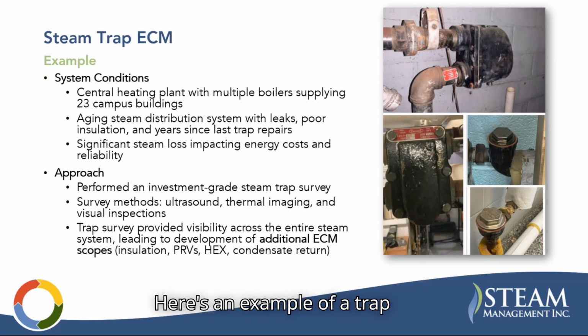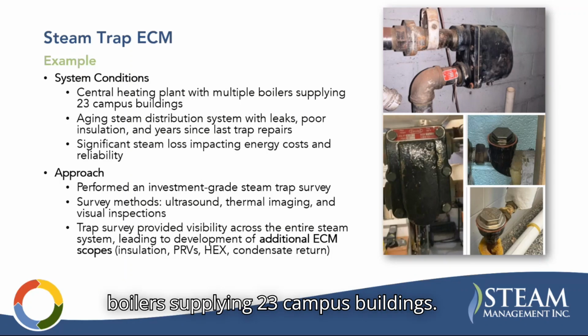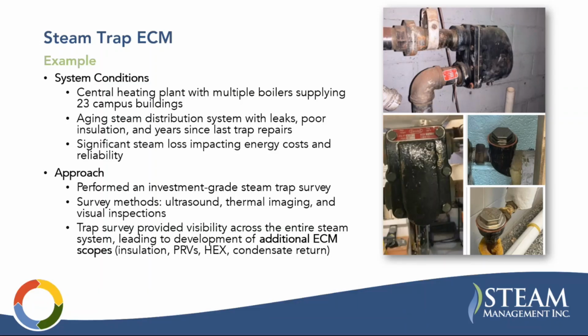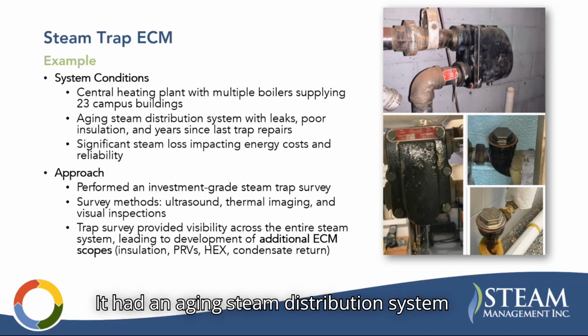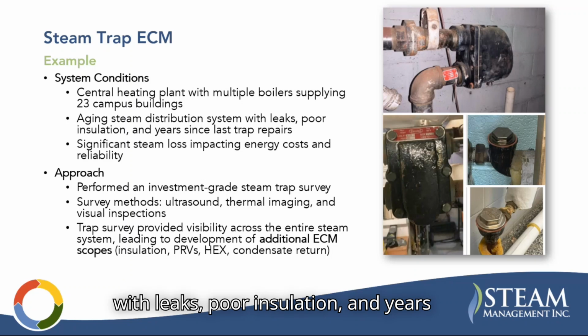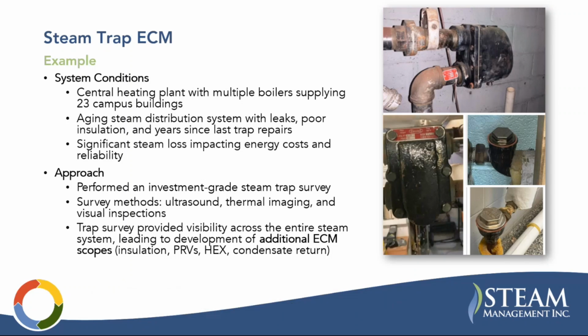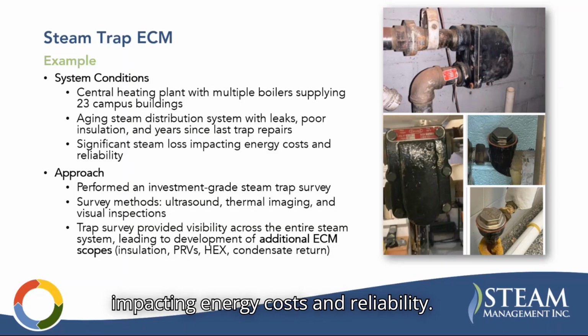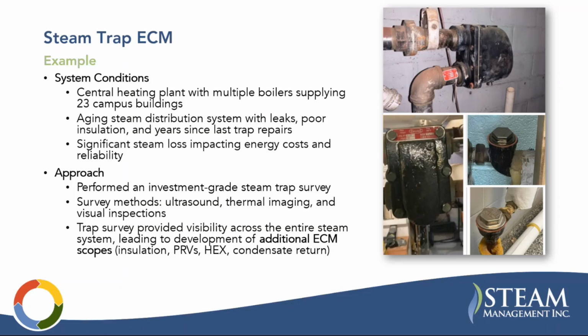Here's an example of a trap opportunity. The system conditions: we had a central heating plant with multiple boilers supplying 23 campus buildings. It had an aging steam distribution system with leaks, poor insulation, and years since the last trap repairs. And then there was significant steam loss impacting energy costs and reliability.